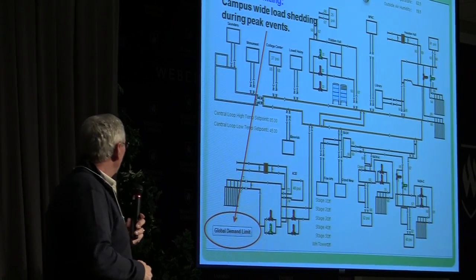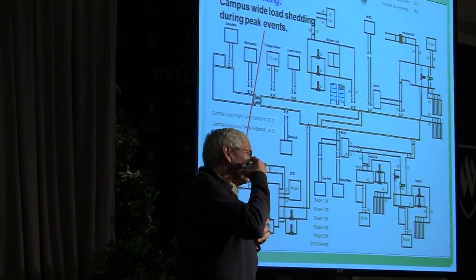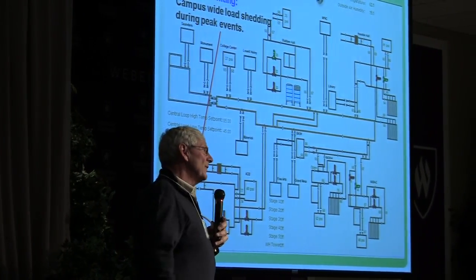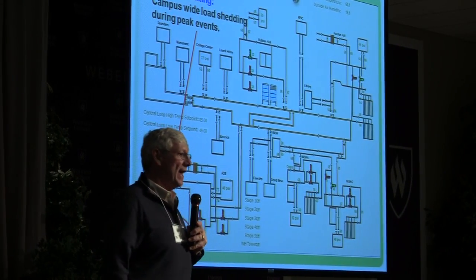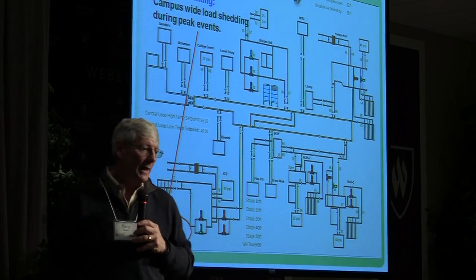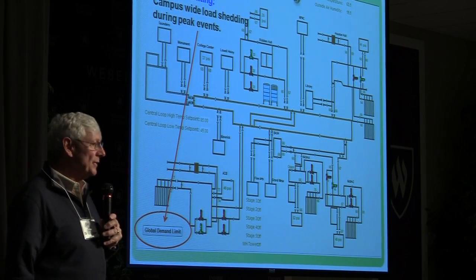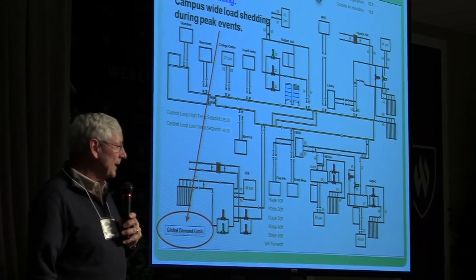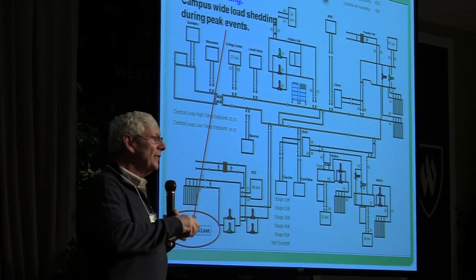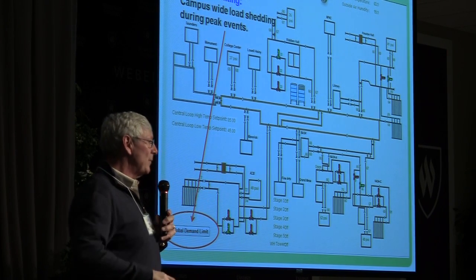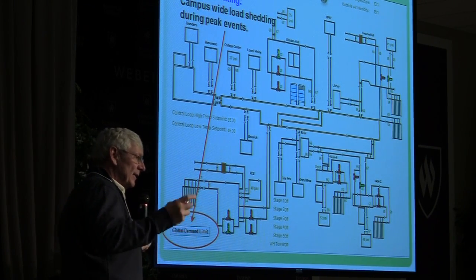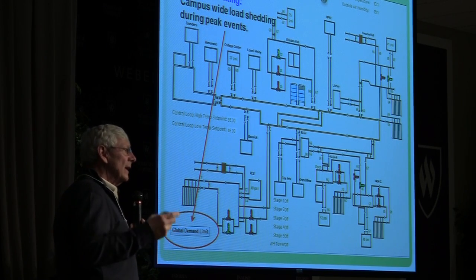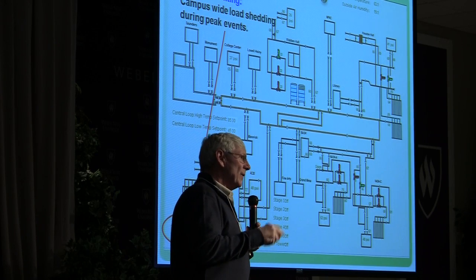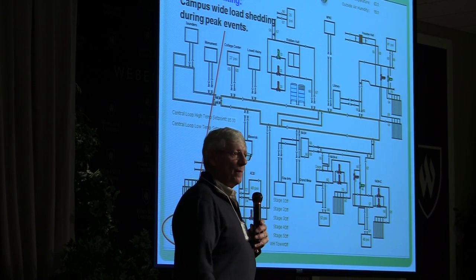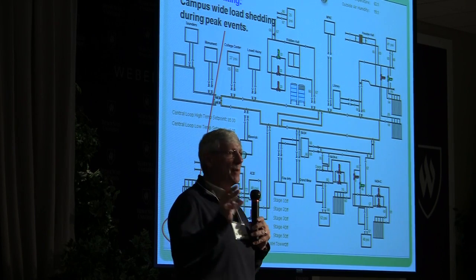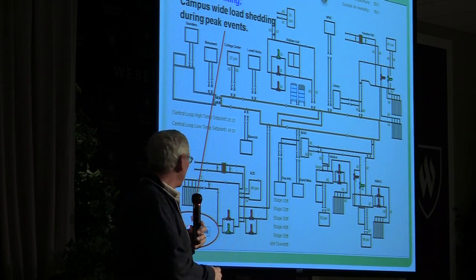We set up a button. Tri-State Generation has a program where they'll call their major industrial customers and tell them they're having a load event, usually in the middle of the summer. The first time this happened while we were under construction, the building facilities manager sent his guys scrambling out around the campus to set back thermostats, turn off outside air, do anything they could to limit the demand, because he was told if he could limit the demand in the next hour, they'd send him a check for $5,000. So we got out there, watched these guys scramble around, and said, hey, we've got a better way to do this. Let's put this button on here called global demand limit.